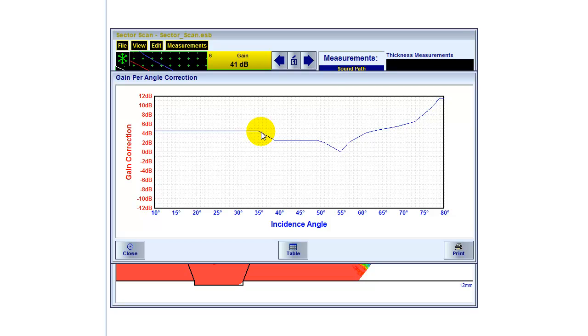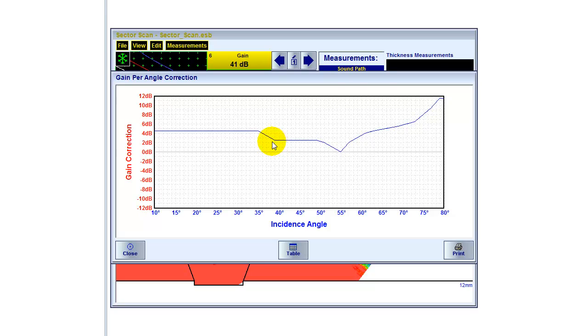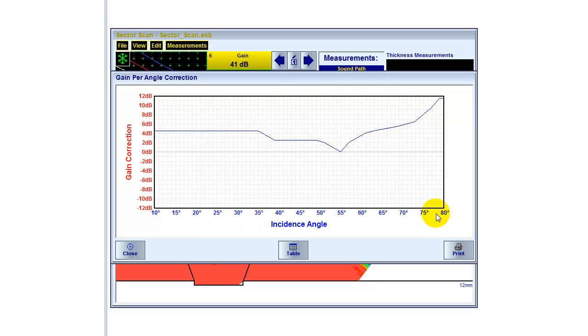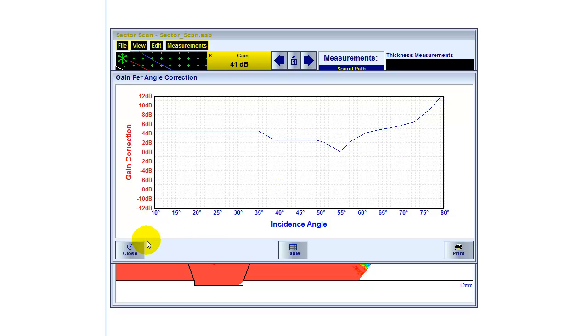So if someone uses a probe the first time, he has to do once this kind of calibration to compensate for the loss of energy, the gain difference over the incidence angle. So once this is stored, it just gets recalled later on for all the following inspections.